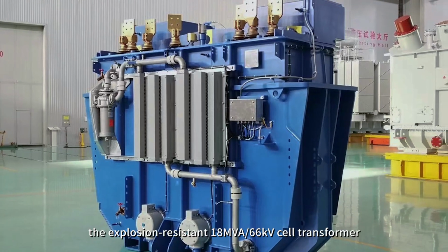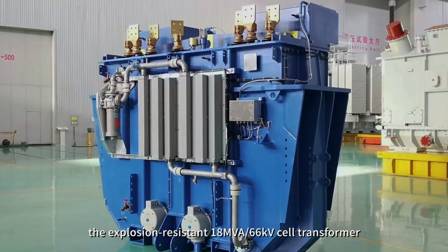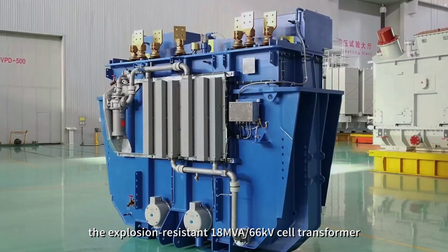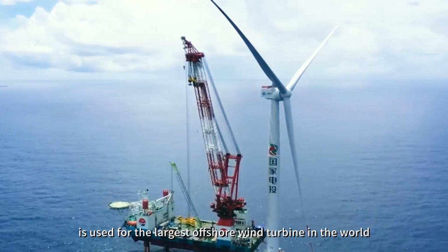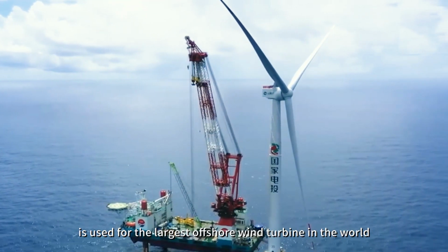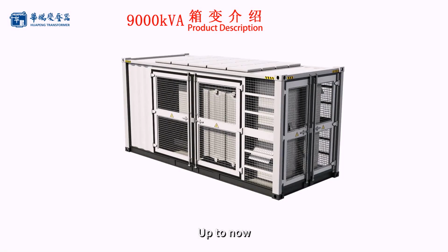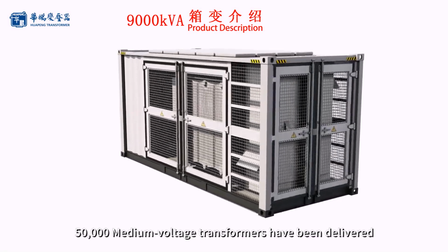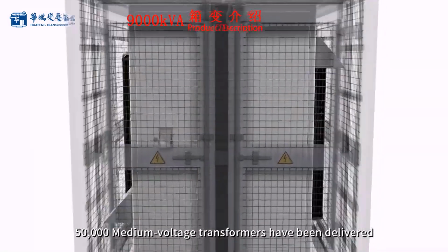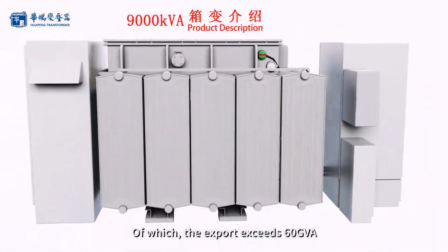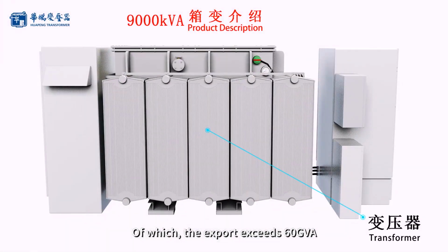Among them, the explosion resistant 18 MVA 66 kV cell transformer is used for the largest offshore wind turbine in the world. Up to now, 50,000 medium voltage transformers have been delivered, of which exports exceed 60 GVA.